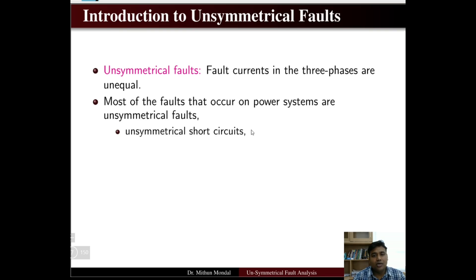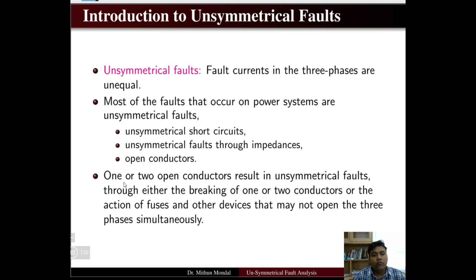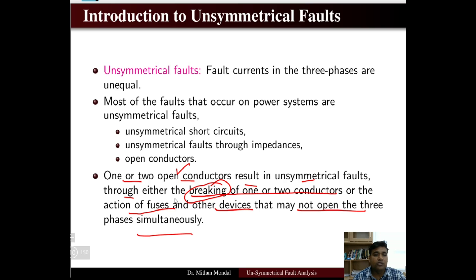These faults occur due to unsymmetrical short circuits in the line, unsymmetrical faults through impedances, or open conductors of the line. When one or two conductors are open, it results in unsymmetrical faults due to breaking of one or two conductors. This can also result from the action of fuses and other devices that may not open all three phases simultaneously, leading to unsymmetrical faults.